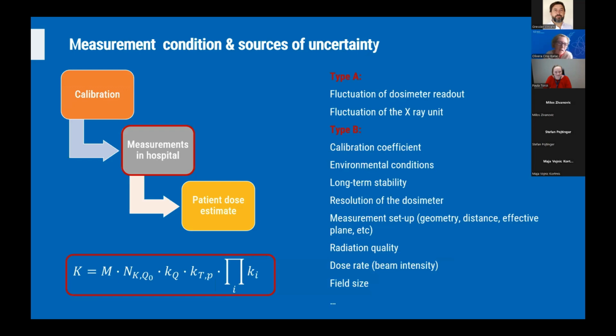But if we go back to the procedure itself, traceability comes through the calibration process and brings up the calibration certificate. This is one input parameter for the measurements in hospitals that is again influenced by a number of parameters related to the setup, environmental conditions, and properties of dosimeters used in the clinical environment. All these parameters can be classified as either type A or type B uncertainties, and they eventually contribute to the overall uncertainty budget of the dosimetry measurements in the hospital.